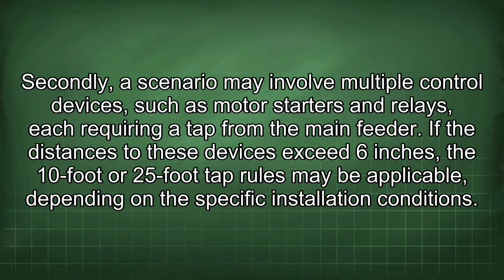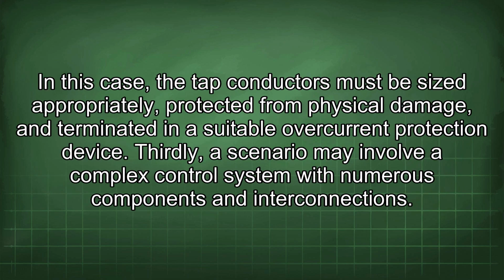Secondly, a scenario may involve multiple control devices, such as motor starters and relays, each requiring a tap from the main feeder. If the distances to these devices exceed 6 inches, the 10-foot or 25-foot tap rules may be applicable, depending on the specific installation conditions. In this case, the tap conductors must be sized appropriately, protected from physical damage, and terminated in a suitable overcurrent protection device.